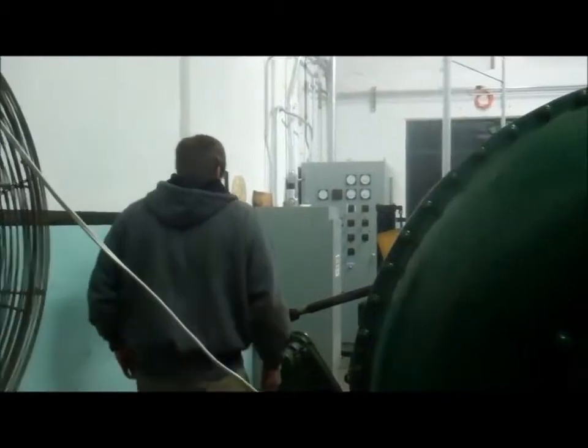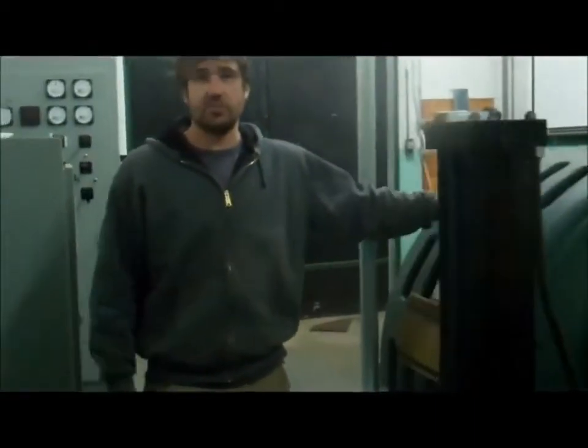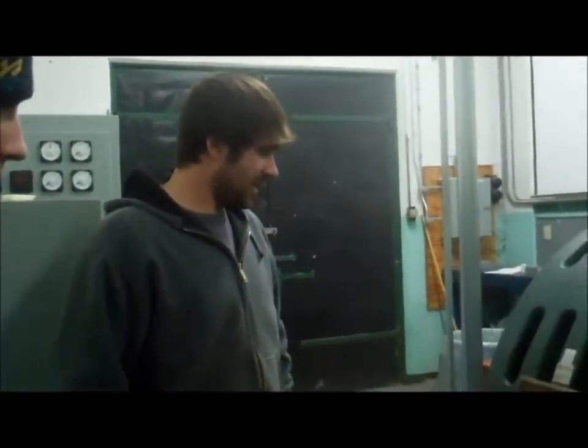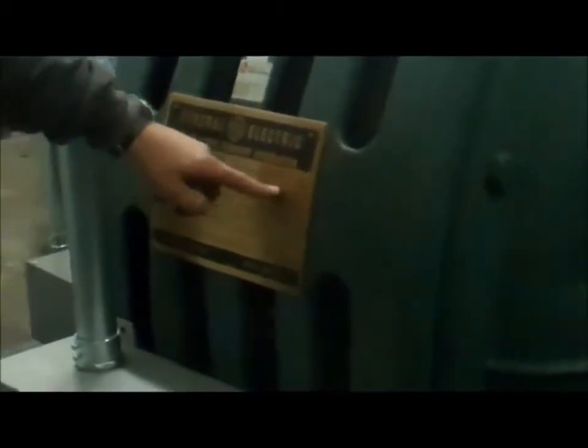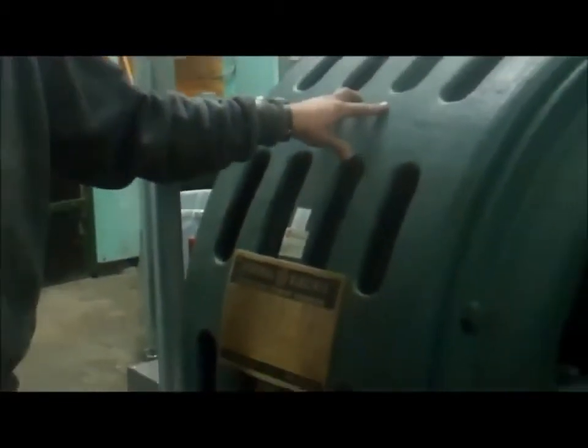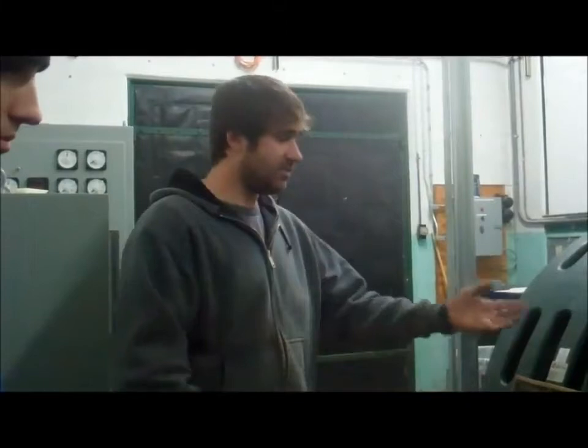And this machine right here, most of our generators are either General Electric or Westinghouse, even though General Electric wanted the DC thing back at the turn of the century. They were still making AC generators. The nameplate on this is 250 kW output, but this machine will actually do 350, and it's because it was rewound. And the modern insulation on the copper wire is that much thinner and that much better that they can fit that much more copper inside the generator itself. So the machine had the power to turn it, so we're actually getting more output out of the same machine.